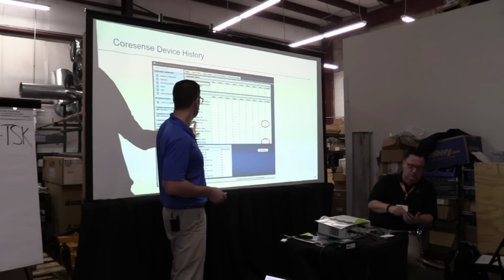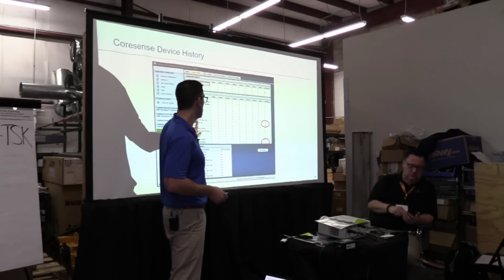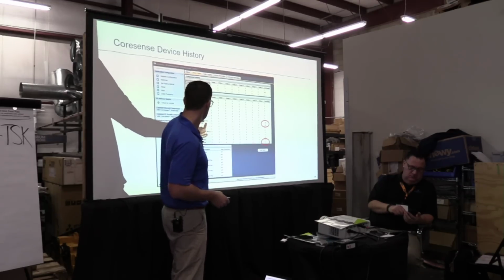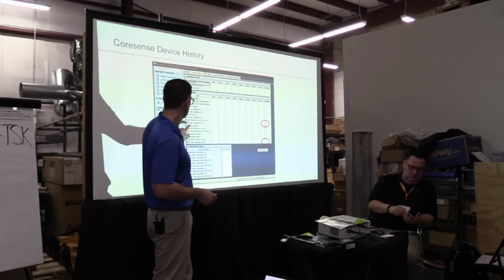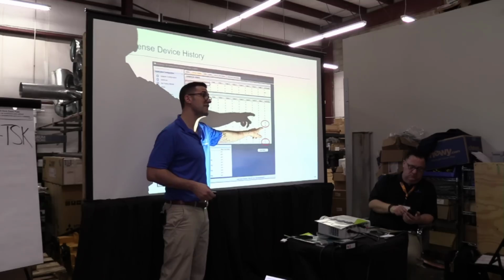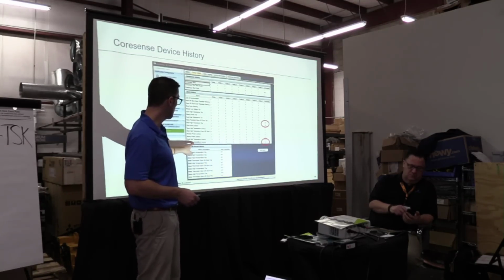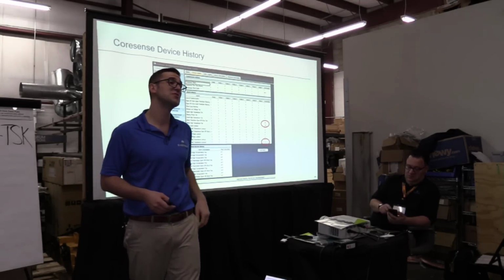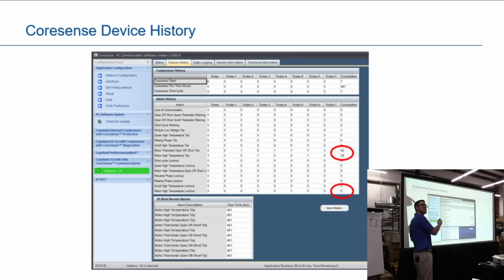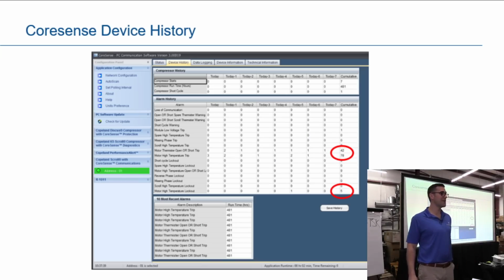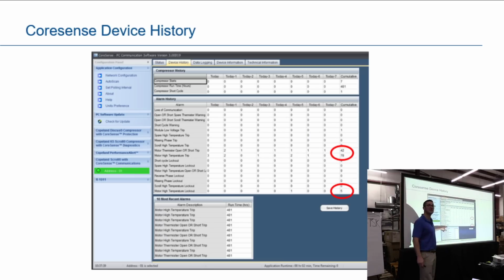Oh, sorry. Motor temperature thermistor, open or short, tripped 42 times. Motor high temp trip, 78 times. Motor temperature lockout, 5 times. So he's telling me this is a problem with the CoreSense. What was the CoreSense doing? Doing its job. How do you think you reset a lockout? Kill the power. So how many times did this person go back there?